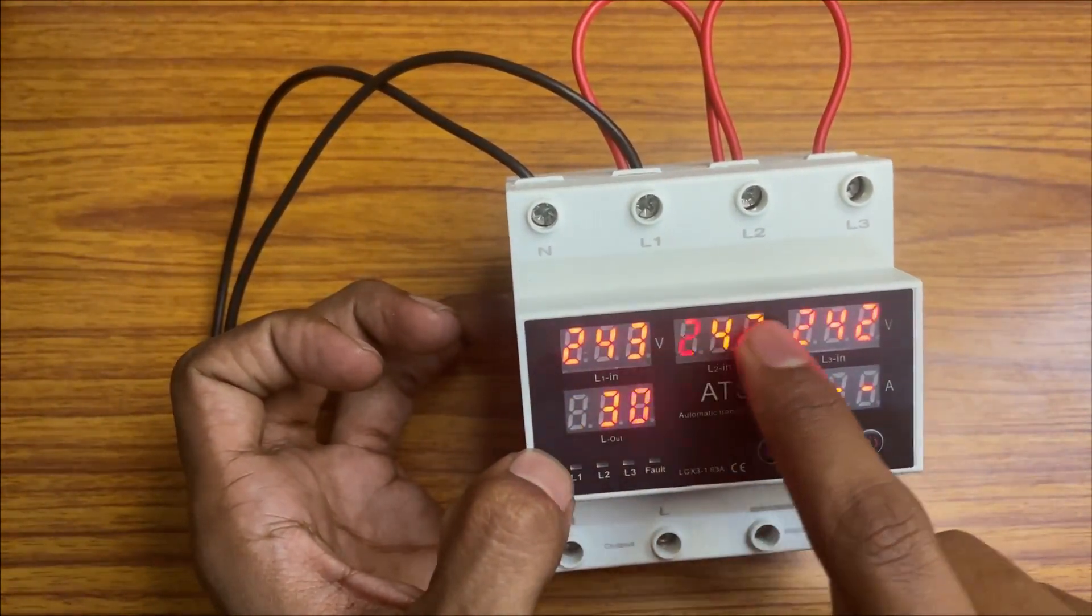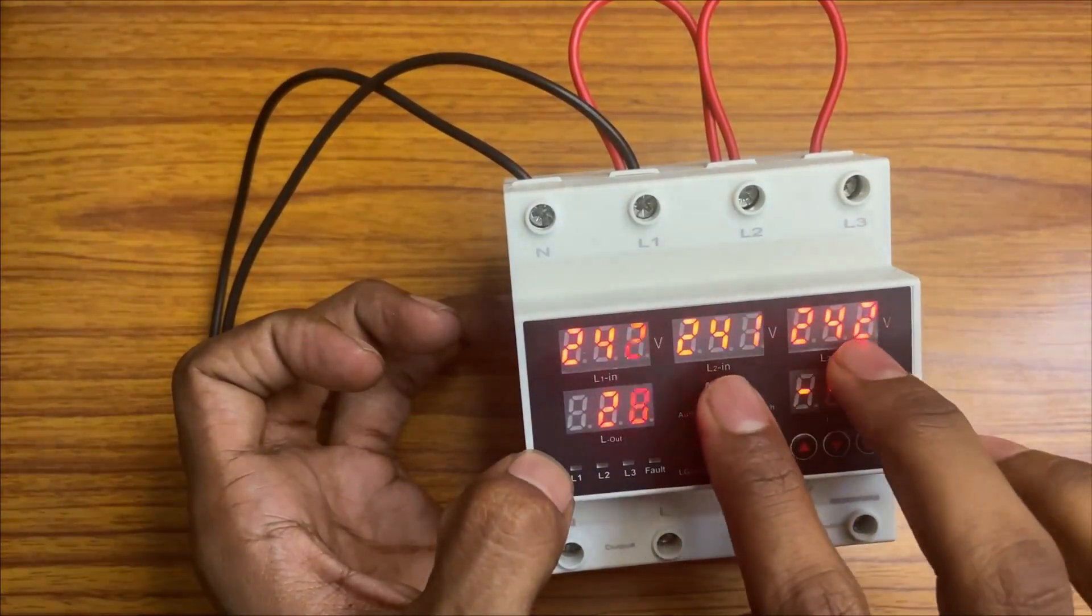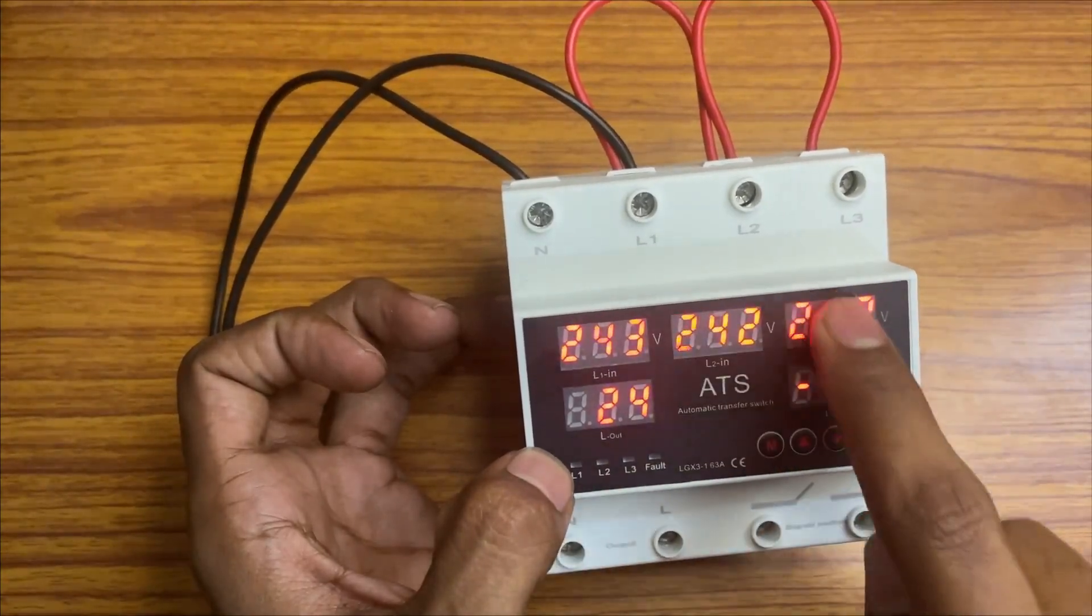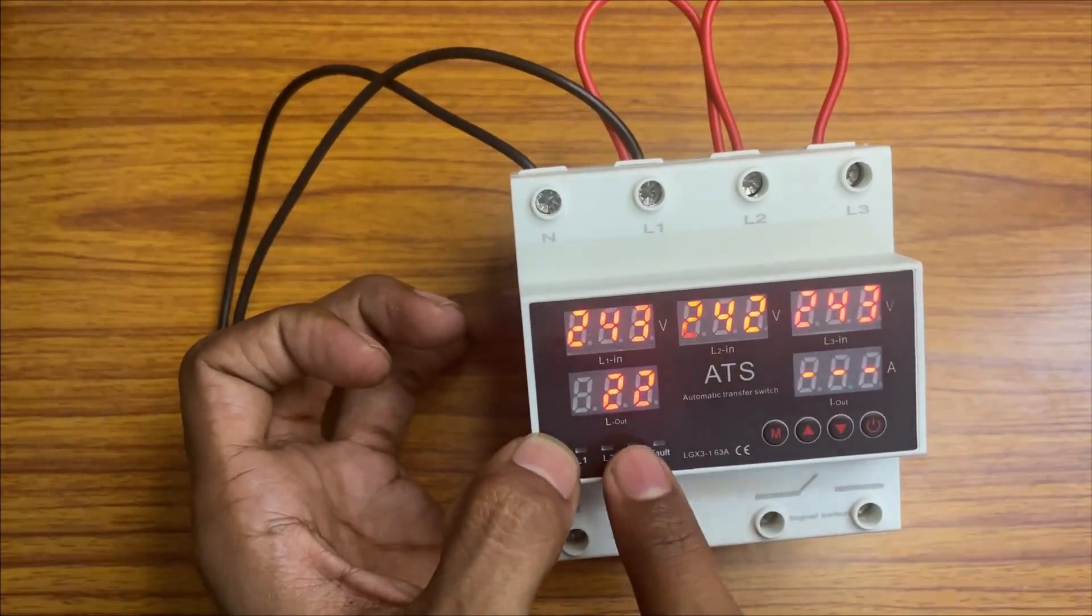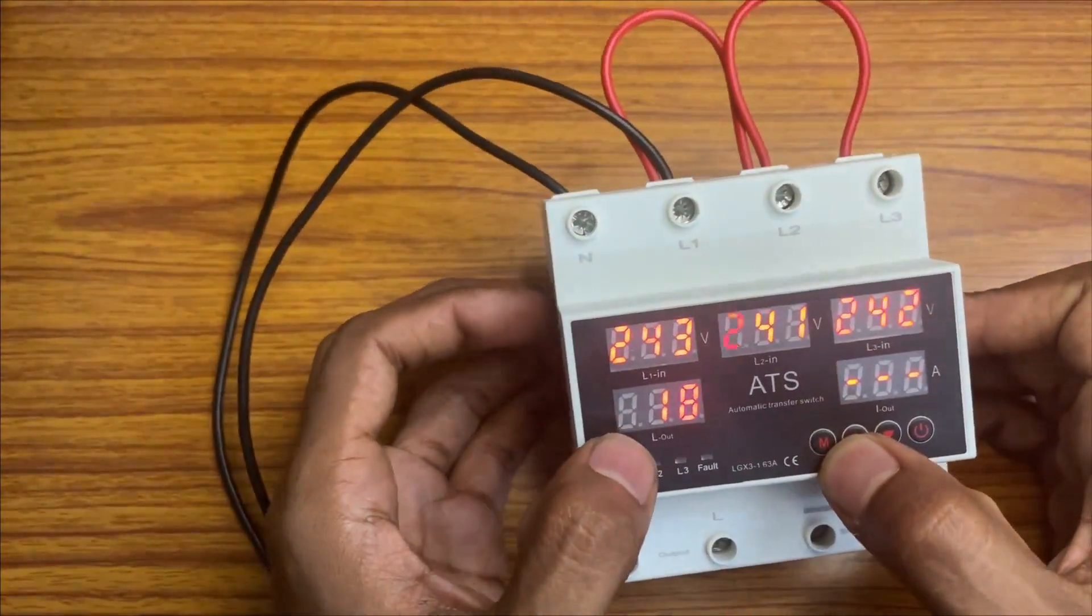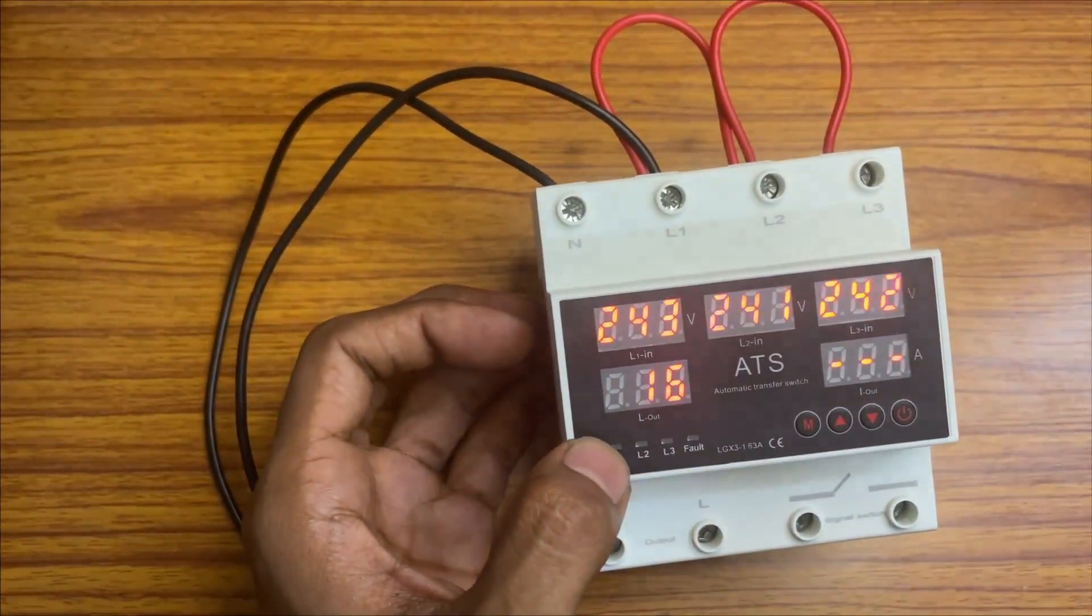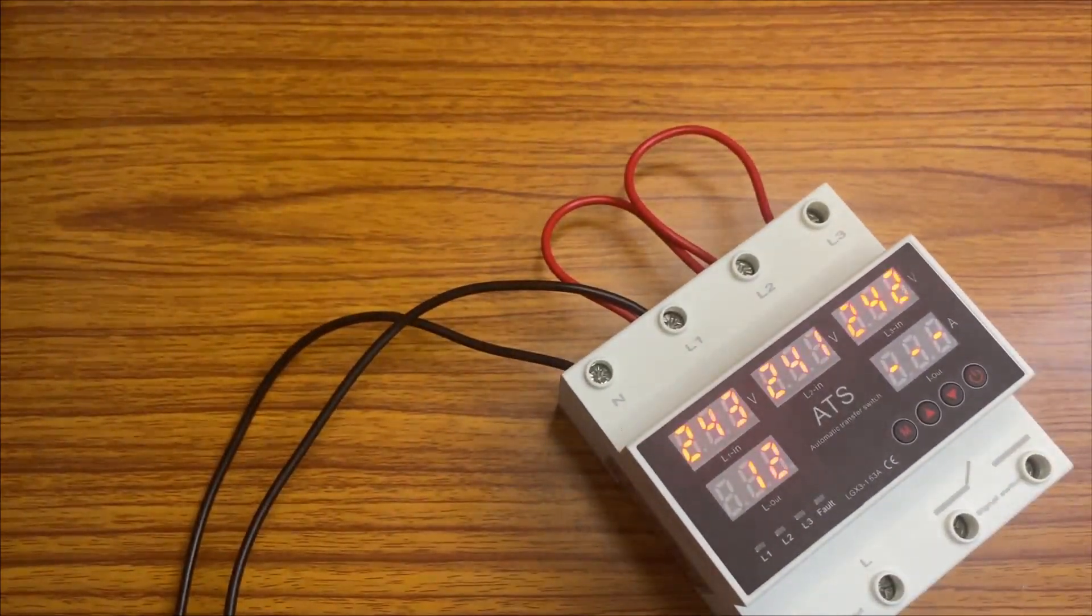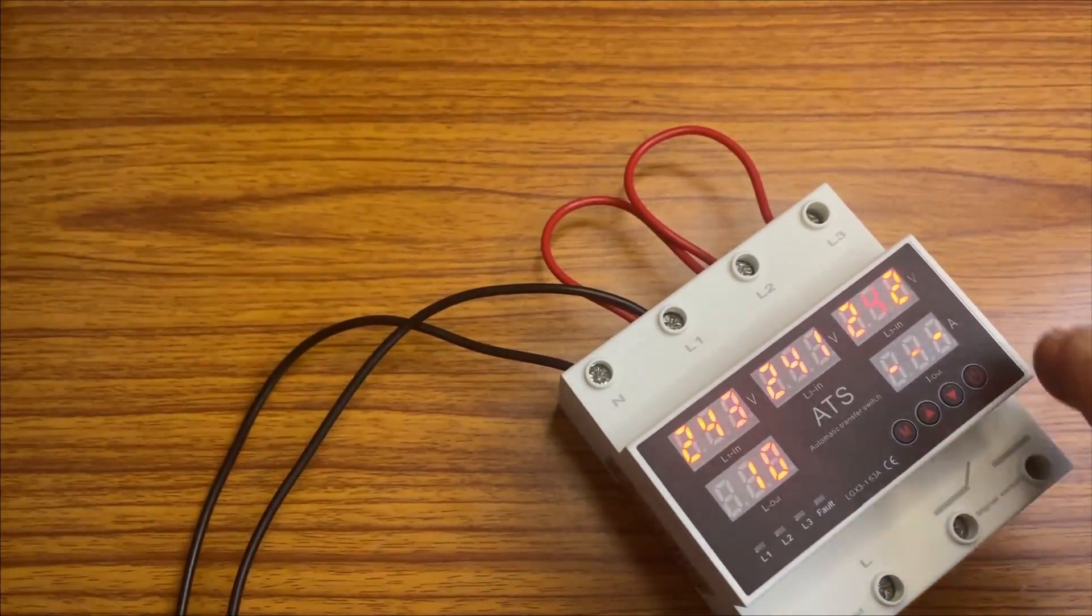This is auto option. Auto option means it will detect which voltage is correct. If you keep it in auto, if one voltage is over voltage, it will check with the rest of the two phases and give the output from that phase. If this is over voltage it will go for this and give the output from this phase. This is the main feature. So we have done the setting like auto.